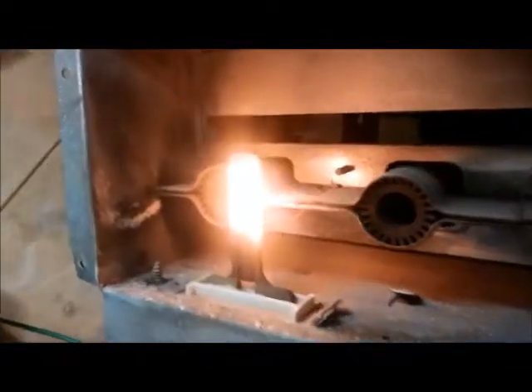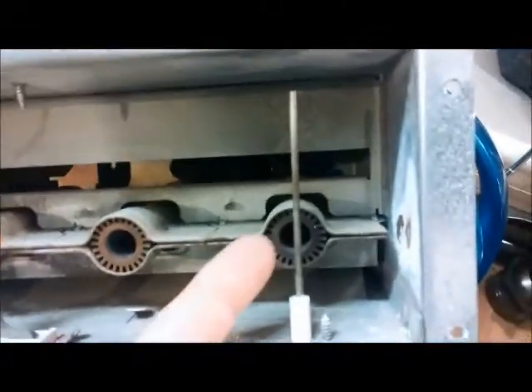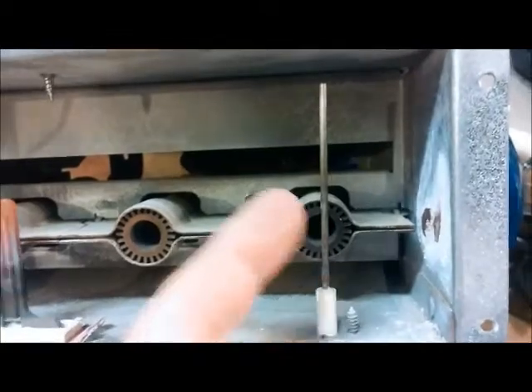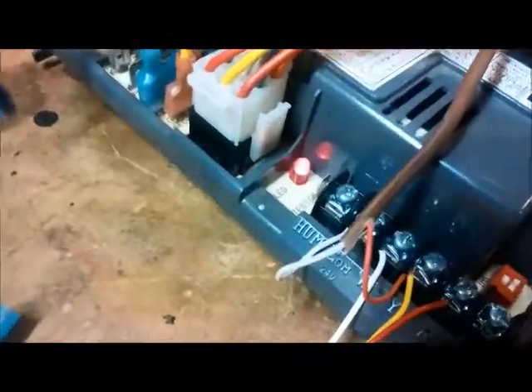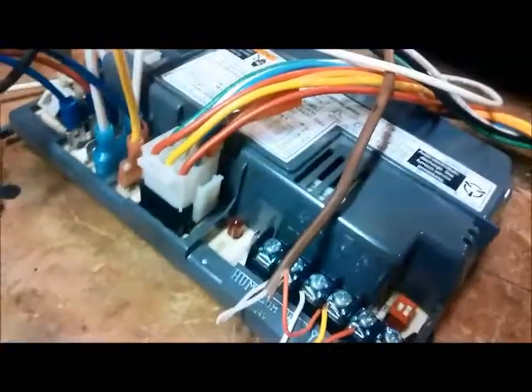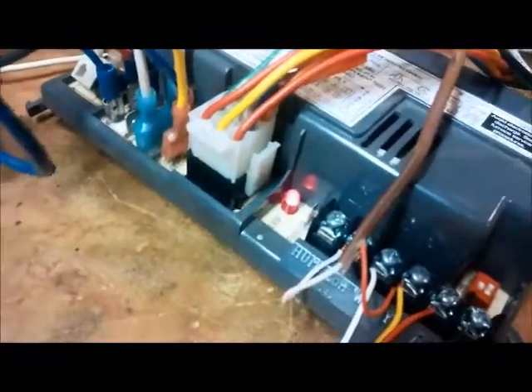And then there we go. The gas valve just clicked. You've got less than a second to prove flame at the flame sensor, which is hooked to this white wire right here. So the flames would conduct current through the flame to that, and then back to the board through probably that white wire. Now we're getting a different fault code because the flames didn't come on. It's going to be probably a 1-4.